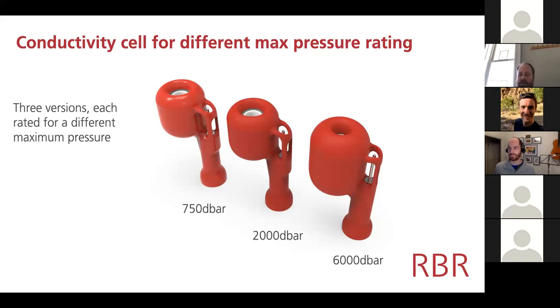All of these have exactly the same specifications. You can see that the thermistor strings are identical. And if you had a very sharp eye, at the beginning of the presentation, when I had a picture of a CTD, you would have noticed that the thermistor string on that one was considerably narrower than this one. That's because the one shown in this picture is actually our long-term deployment string. It's made out of titanium. It has a time constant of about 700 milliseconds. I think on the data sheet it says less than 1 second, but it's about 30% better than that. And because it's titanium, there are no corrosion problems ever.